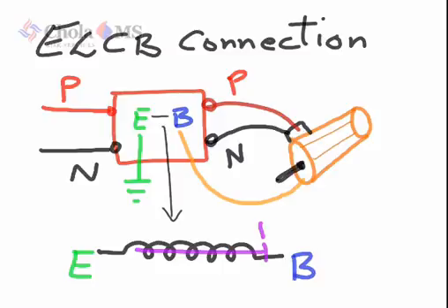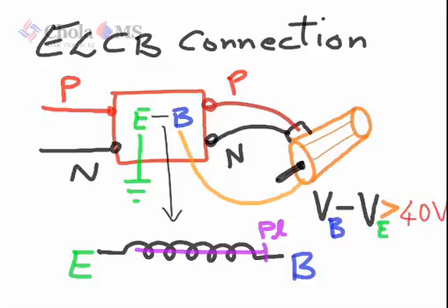There is a plunger operated by the solenoid which works when motor body voltage is 40 volts greater than the reference earth voltage. This is when the ELCB trips. Thanks for watching.